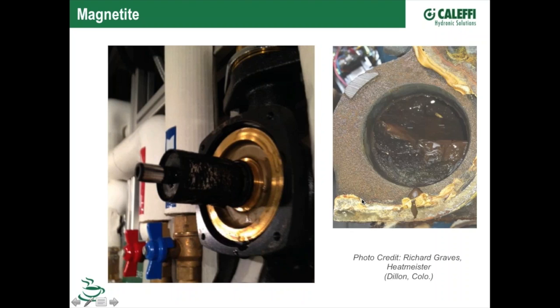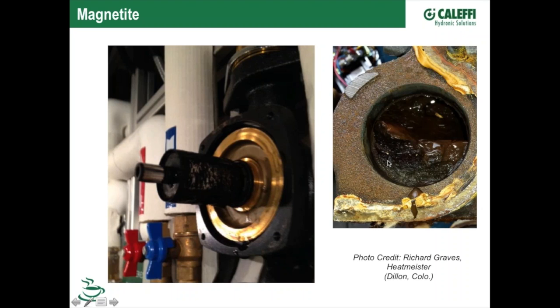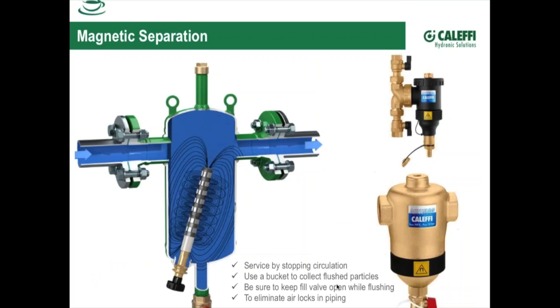Worst case scenario, if you get a lot of that, it's going to settle to the low points in the system. Here's a boiler that was taken out of a job where the entire system had started sludging up. And when he took the boiler apart, that's what was in there. If you take that debris out and stick a magnet to it, if it sticks to a magnet, this is what you've got going on in there. And that's typically going to be caused by oxygen getting into the system. That's what can develop this condition. And if you've got oxygen getting into it, obviously you need to address that. That could be through a non-barrier tubing or something like that.